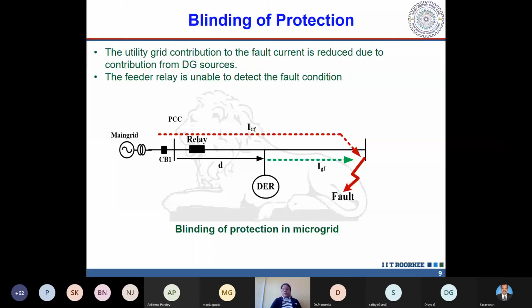in front of those inverter based renewable sources, the fault current magnitude is automatically clamped to 2 per unit. Understand why? Because for the protection of the inverter devices, inside the inverter we have power electronics devices like IGBTs or GTOs or diodes. To save those power electronics devices, there is a clamping circuit present. The controller is also present, and it will try to clamp the current magnitude to 2 per unit.